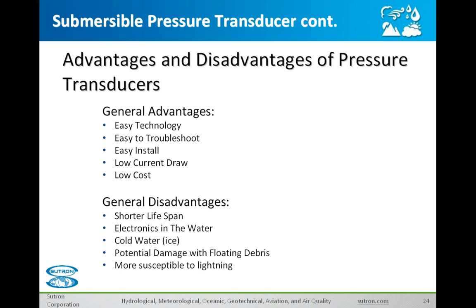As for disadvantages: as we've seen over the years — and I'm in repair so I know this — generally if you get five years out of a pressure transducer, that's good. You may get a little bit more than that, but some other sensors like bubblers we've seen at 15 years old and still going.